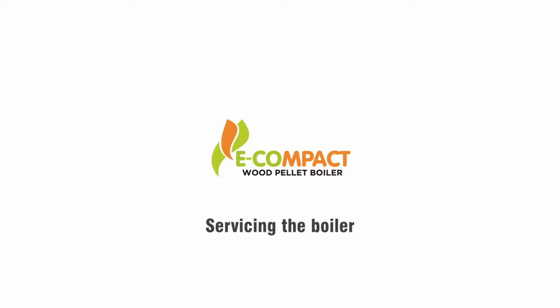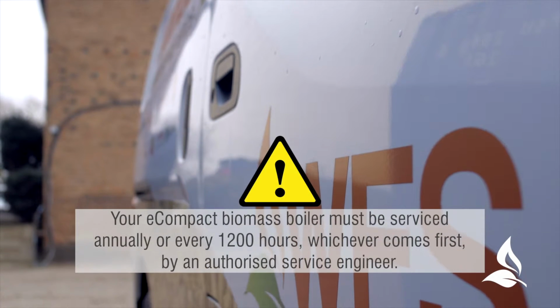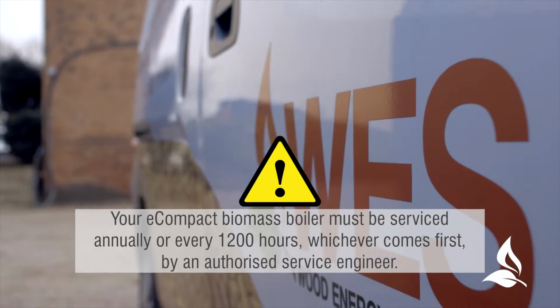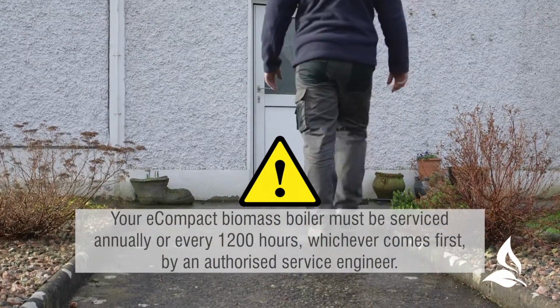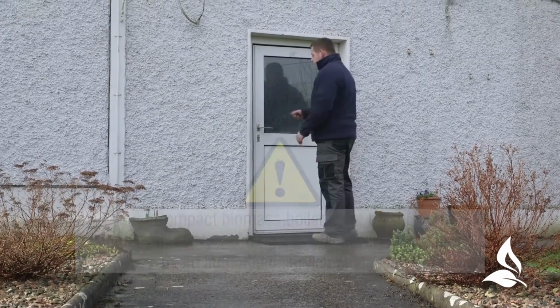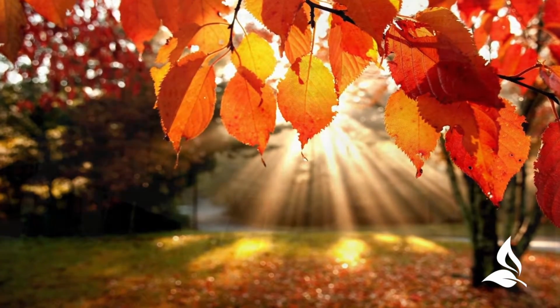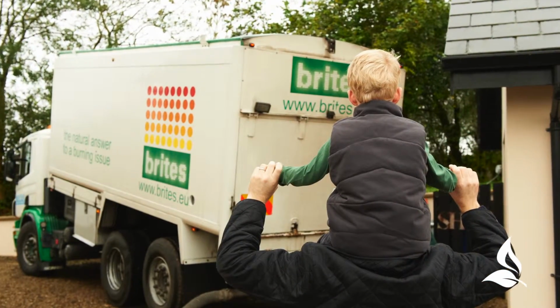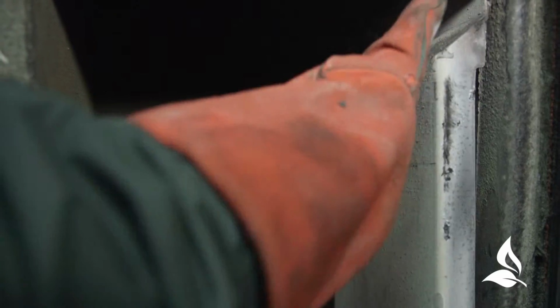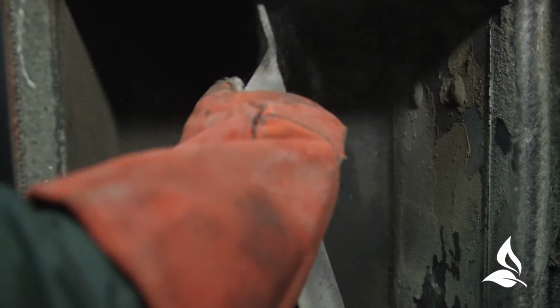To ensure the efficient and reliable operation of your eCompact biomass boiler, you will need to have it serviced annually or every 1200 hours, whichever comes first, by an authorised service engineer. We also strongly recommend that before the heating season the boiler receives an interim service, which entails cleaning the heat exchanger, and this is carried out by the service provider.